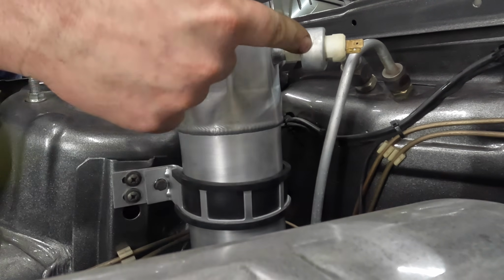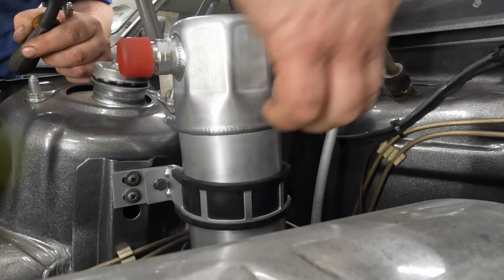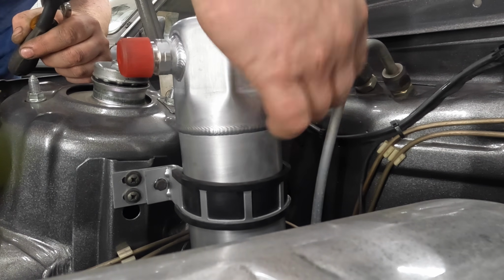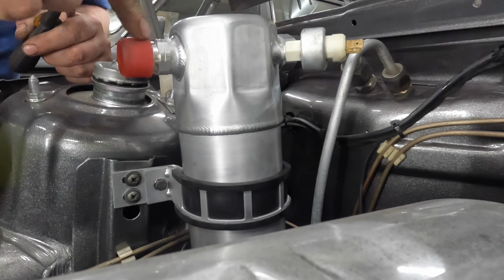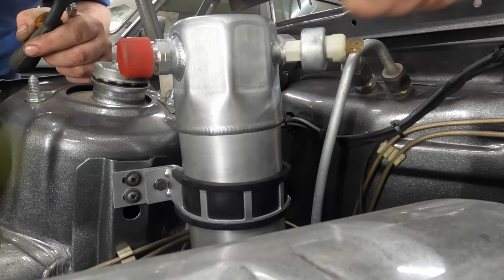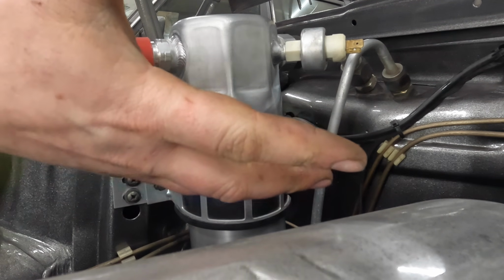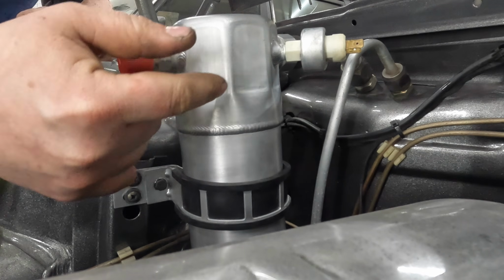You'll also see this guy right here. This is a pressure switch, what cycles the compressor on and off. I'm to assume that's to prevent the compressor from picking up liquid refrigerant, because if that happens, that can break stuff. You only want gas going into the compressor.